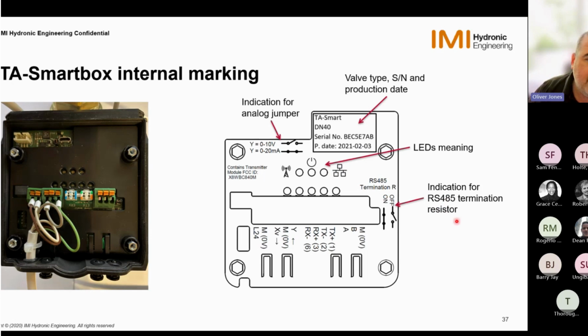Then we have our RS485 termination resistor. So just in this section here, there's a little jumper. So we just need to change the jumper on the last unit. So if we're using a physical layer Modbus or BACnet, so RTU or MSTP, on the last unit of the run, we have to make this contact. So this resistance is included. So we have a 120 ohm resistance at the start, and this replicates 120 ohm resistance at the end. So it knows that this is the last valve in the sequence, or in the circuit, I should say.